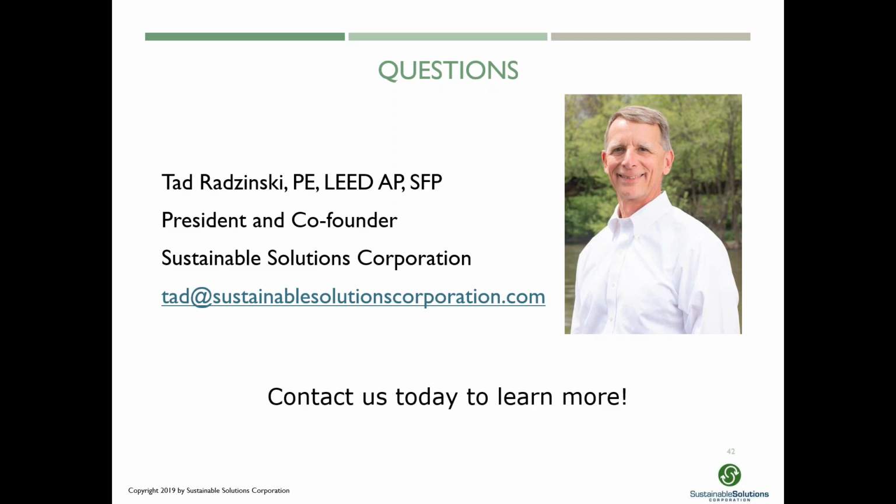I can tell you that anything done in the BAS, if it's only a programming change and you have someone who knows how to do it, whether you're contracting with someone to run your BAS or you have building engineers that do it, it is the lowest cost thing you could do, and it can provide tremendous savings. We've identified opportunities most recently in buildings to save anywhere from $5,000 just from BAS changes up to $300,000 to $400,000 a year just by adjusting things within the BAS. So that's a huge one.